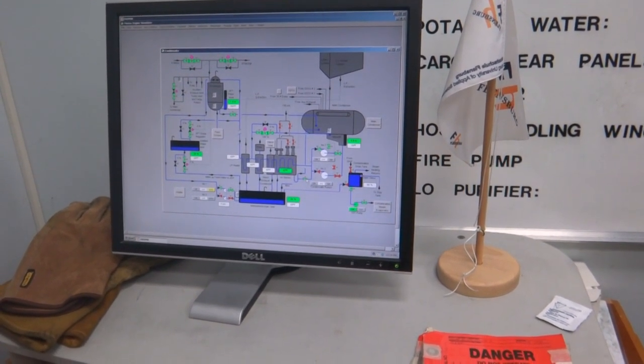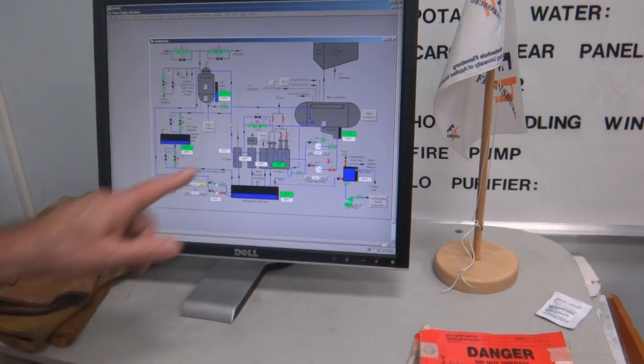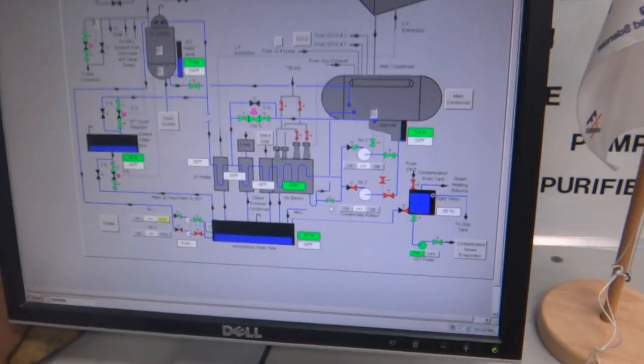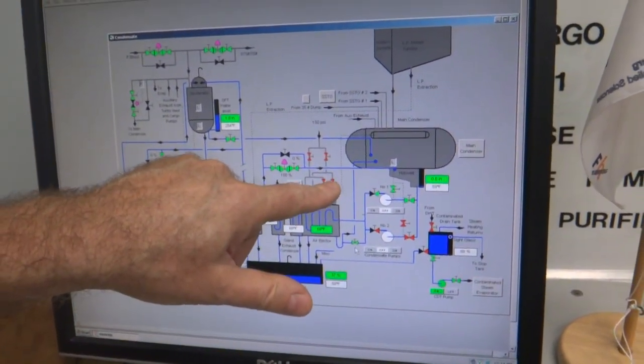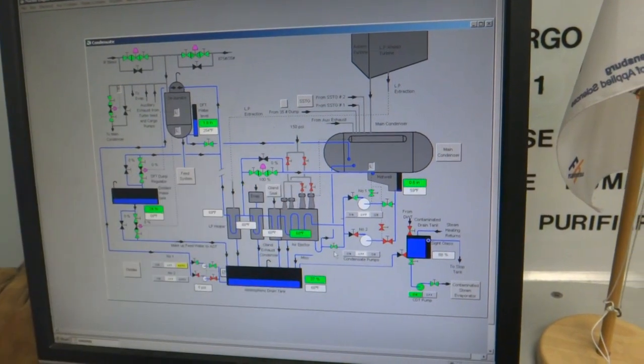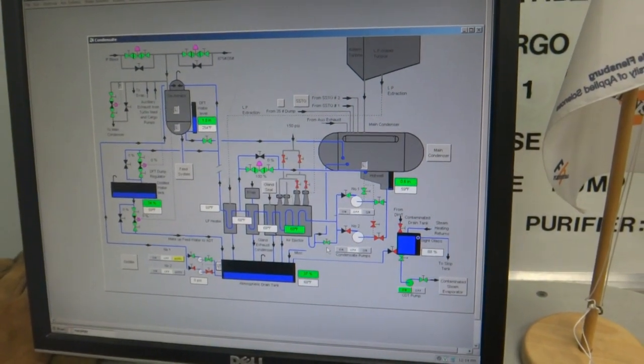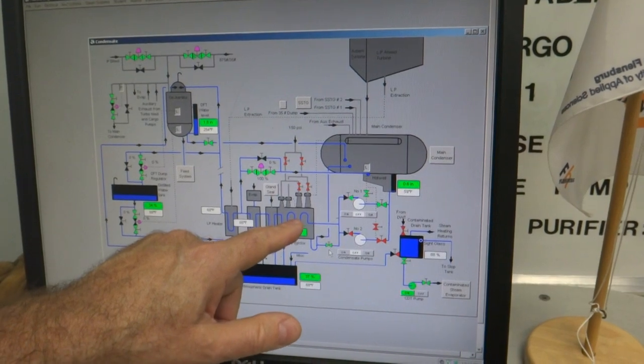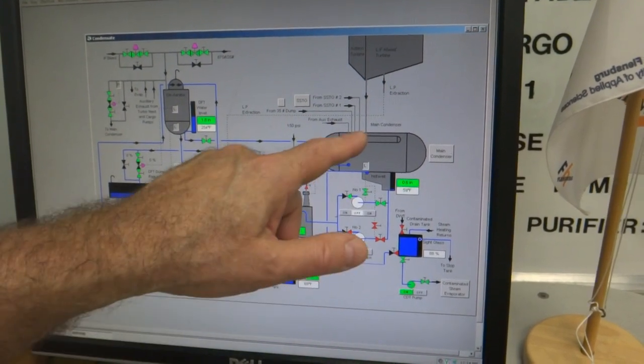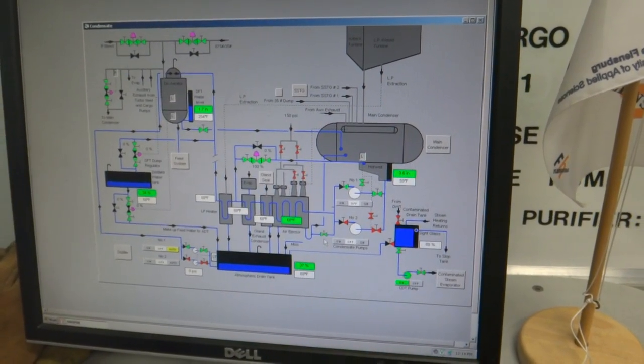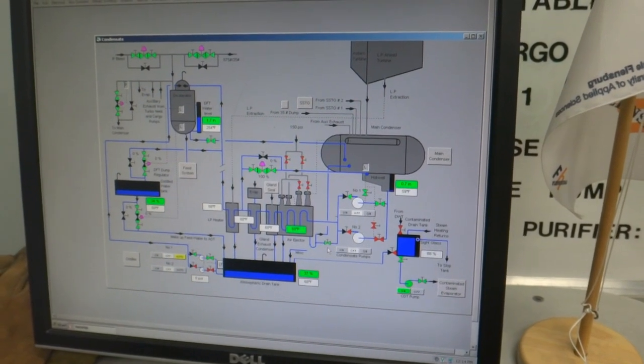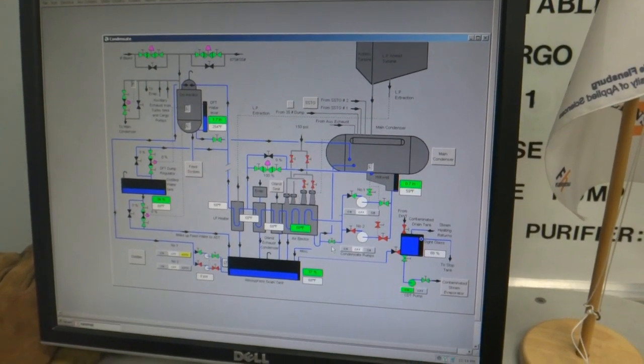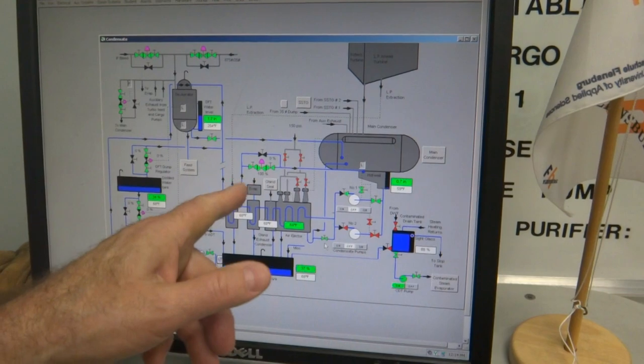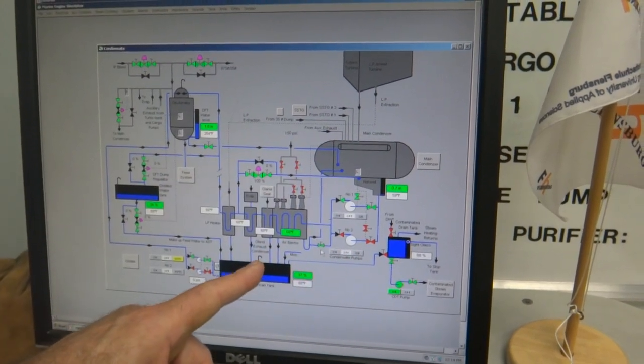This is a charging line for the loop seal. The loop seal is about 8 feet tall. It's all the condensate from that first stage going back by vacuum drag to the condenser. There's a pressure difference between the inner condenser and the main condenser. If you don't have the loop seal charged initially, you're going to have trouble. You're going to lose vacuum because it's going to equalize and pull in some air.